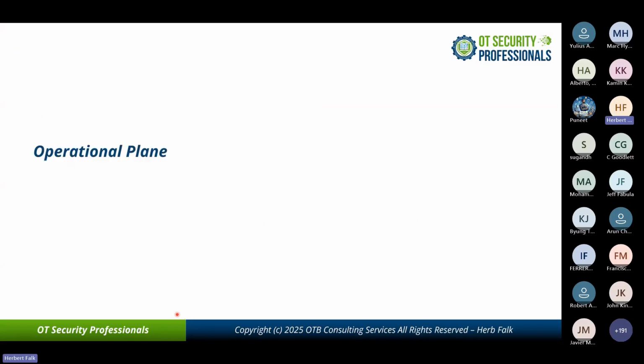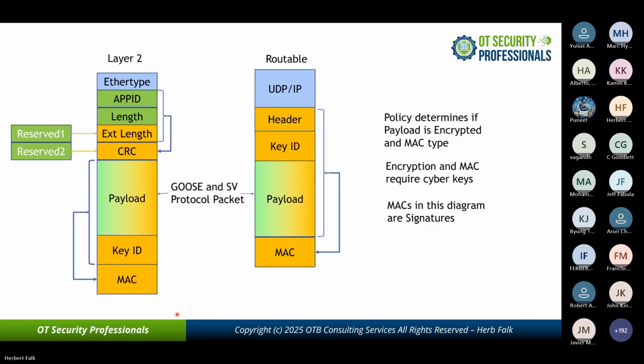Let's talk about the operational plane, because this is where protection actually occurs. We've added security to layer 2 GOOSE and, obviously, for routable GOOSE. The policy that gets delivered by the KDC over the management plane tells you if encryption is going to be used. And for layer 2 GOOSE, it tells you if security's even in place.